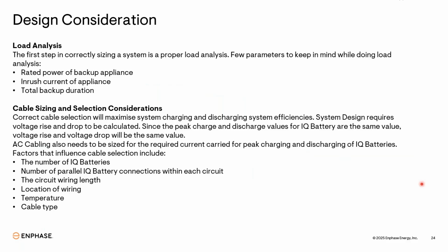Whenever you approach a homeowner, there are a few things you need to keep in mind. You need to explain to him the number of hours he wants backup and the essential loads he wants to back up, whether lights or other loads. And you need to make it clear that once you increase your backup consumption or your backup time, your battery sizing counts will increase. So you need to consider the number of batteries, the number of parallel battery connections within each circuit, the circuit wire length, location of wire and temperature, and cable type. All these factors you need to keep in mind, and these factors also help in designing the AC cable sizing.